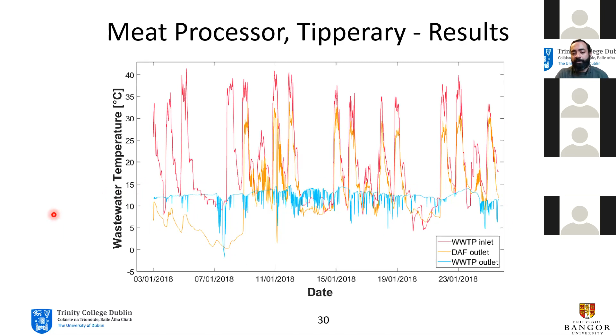So in terms of feasibility, we saw very good feasibility for the meat processing plant at least. So in the outlet of the DAF tank with direct heat recovery, so with those vertical heat exchangers or other similar commercial copper heat exchangers, we would start seeing very low paybacks of 4 to 5 years. And similarly, if we used a hybrid system, which was sort of using both heat exchanger and heat pump together, despite the high installation costs, we still were getting great savings and an even lower payback period. This is just because the heat pump is able to extract so much more of the heat than the heat exchanger that it can offset a lot more of the costs essentially. So at this sort of scale, it's really ideal to have a heat pump in there.